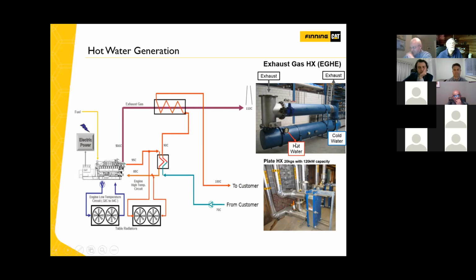So if you look at the exhaust gas heat exchanger, you will see there is a bypass damper. So if we did want to run the genset in power only, we can close this damper. We can bypass this bit, and the exhaust flow will go that way, straight to the exhaust stack and not touching the heat recovery part. And you can see from here, cold water in comes along the tubes, and hot water goes back to the plant. And again, exhaust flow goes against the fluid flow.